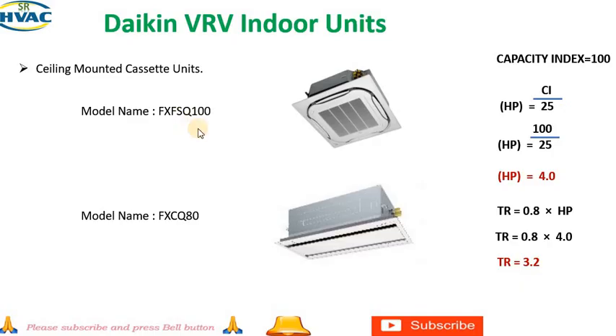Every indoor unit has its own capacity index or CI value. If you want to find the HP of this one, just divide by 25. You will get the HP. Suppose it is 100, you divide by 25, it will be 4 HP. And if you multiply by 0.8, you will get the TR. For this unit it will be 3.2 TR. You can take a copy, you can write this one. This is very important to find the TR or HP of a particular system.